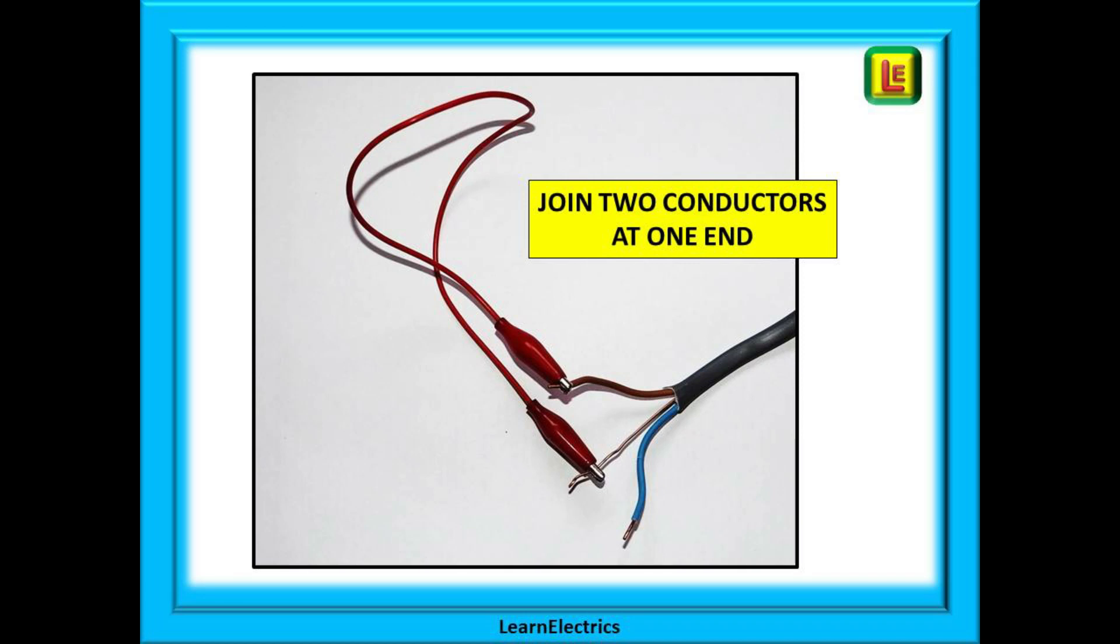How do we do this then? First step at one end strip back the brown conductor and join it to the earth conductor. I use crocodile clips, some people use terminal strips, others use WAGO connectors. Whatever you do just join the two cables together.